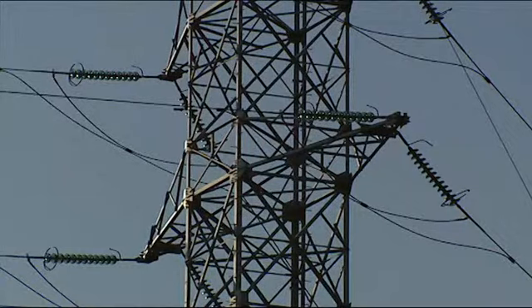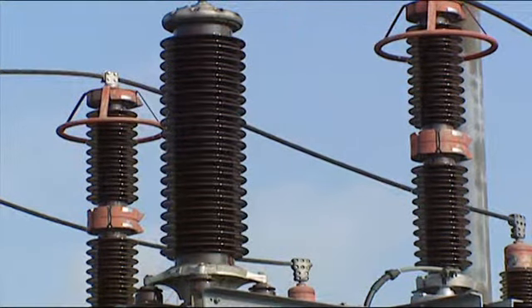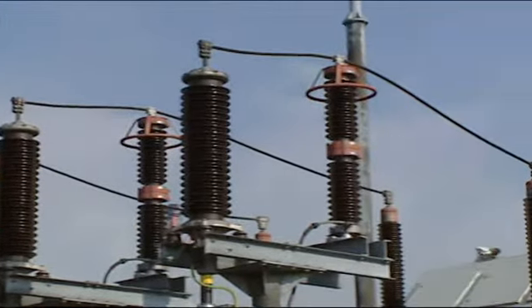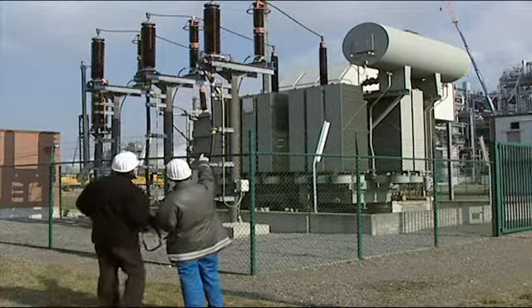Thermal imaging cameras are also commonly used for electrical high-voltage inspections. As electrical connections become loose, there's a resistance to current that can cause an increase in temperature. This can then cause components to fail, resulting in unplanned outages and injuries. In addition, the efficiency of an electrical grid becomes low prior to failure. Thus, energy is spent generating heat, causing unnecessary losses.